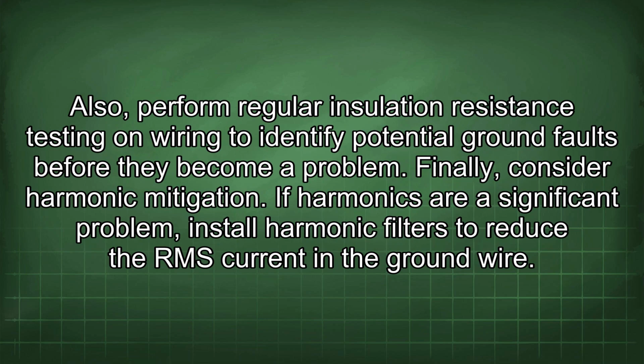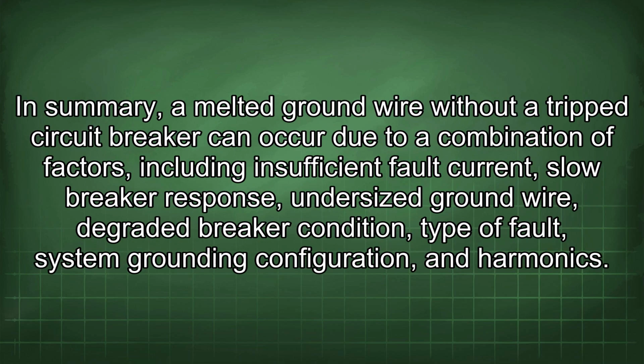Also, perform regular insulation resistance testing on wiring to identify potential ground faults before they become a problem. Finally, consider harmonic mitigation. If harmonics are a significant problem, install harmonic filters to reduce the RMS current in the ground wire.